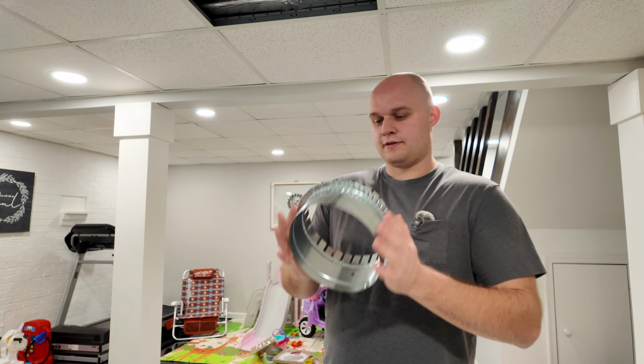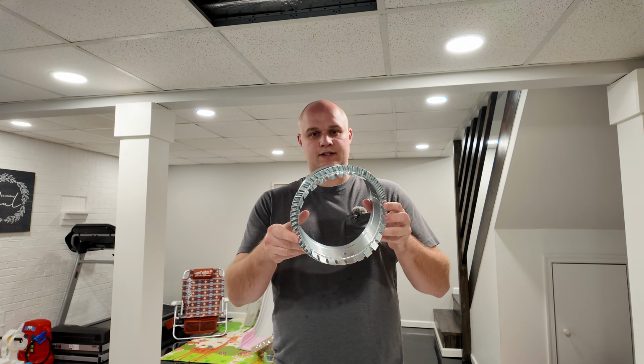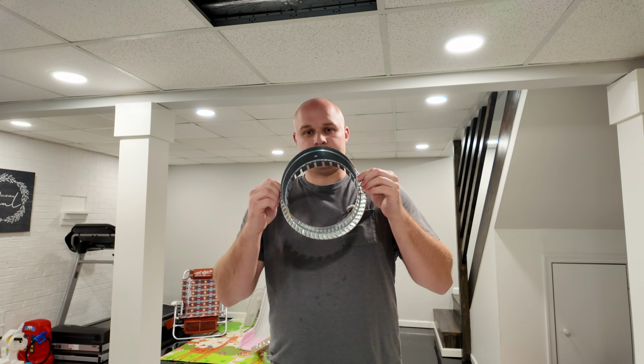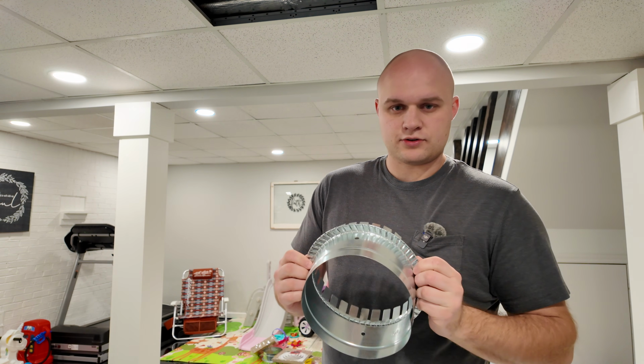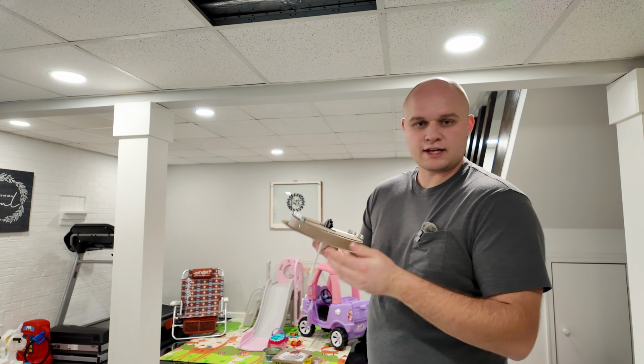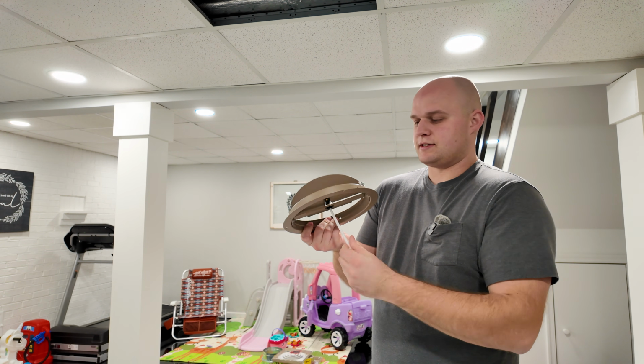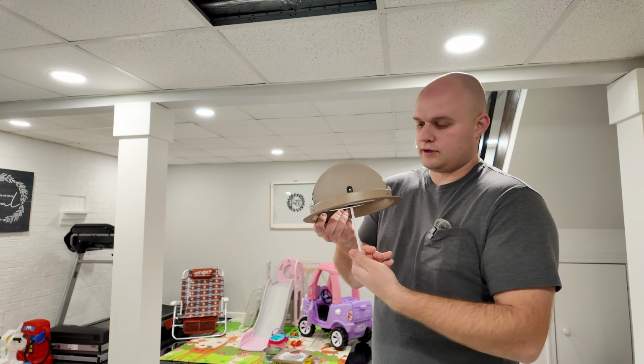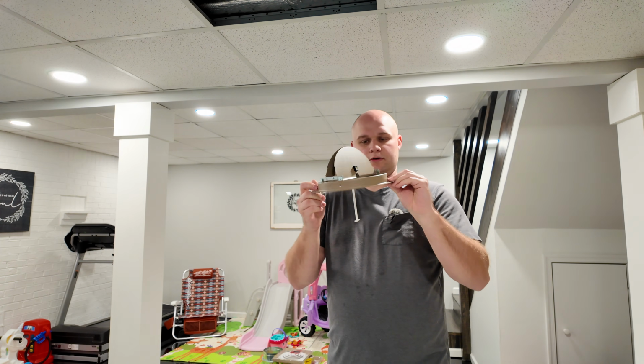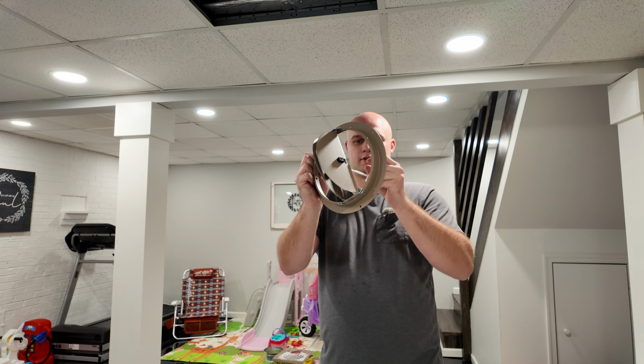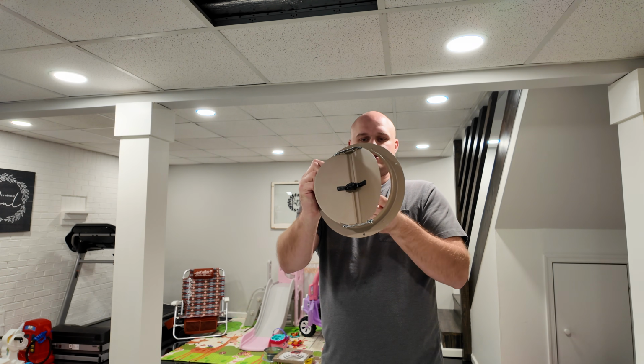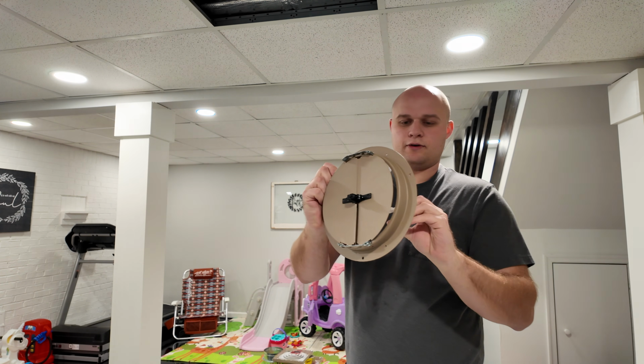So in order to do this project, you're going to need 3 different things. The first thing is this 8-inch diameter takeoff line. This is what's actually going to go into the trunk line itself. The next thing you're going to need is this 8-inch round diffuser. Essentially this is a valve to open or close to either allow airflow or stop airflow, and it's also essentially a damper so that you can control how much air is flowing into the room.